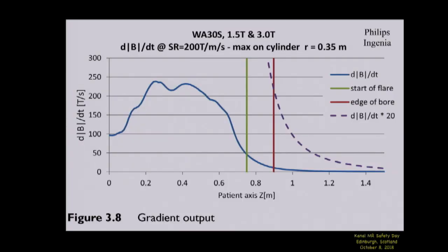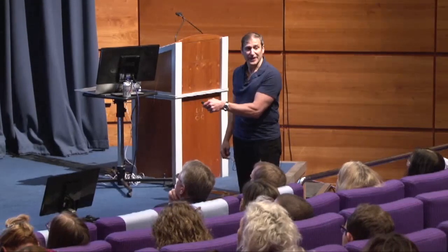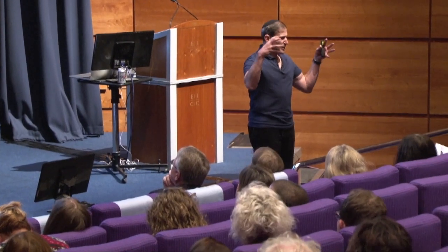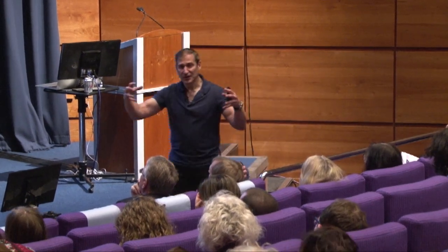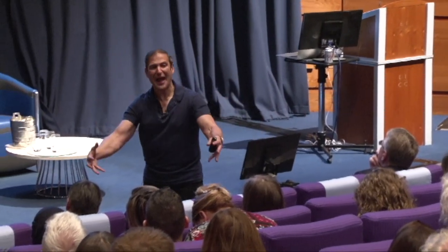And just like we have plots for dx and for B0 and dBdx, we also have plots for dBdt. And this is one manufacturer's plot of the gradient coil. Remember, the gradient coils are epoxied into that MR scanner. You're not going to play with those for clinical systems. The left-right, supra-inferior, anteroposterior gradients are epoxied, bang, they're stuck in there. You don't even see them.